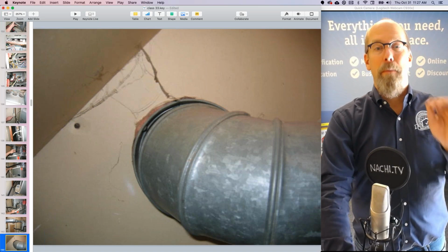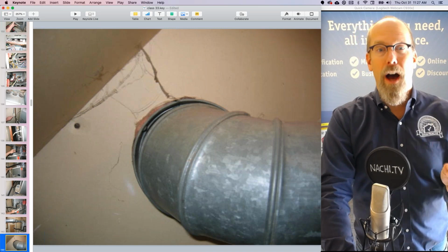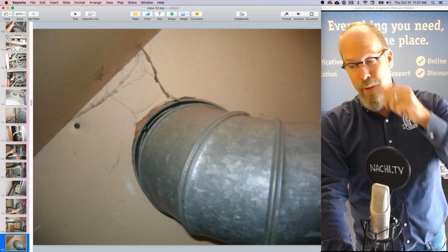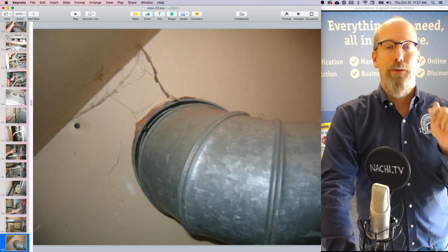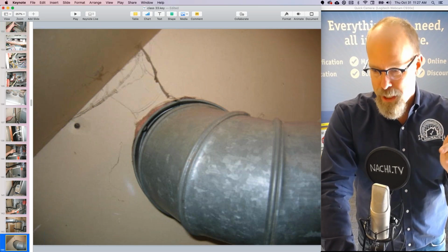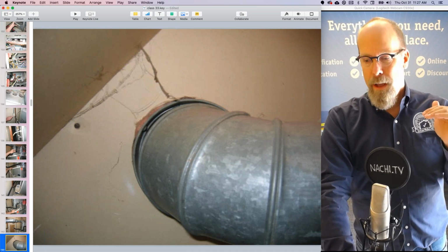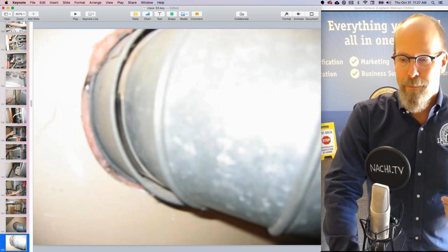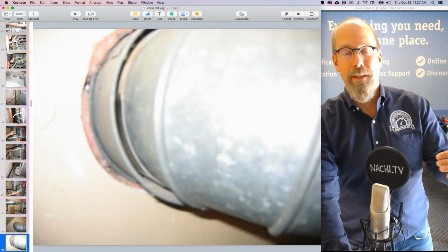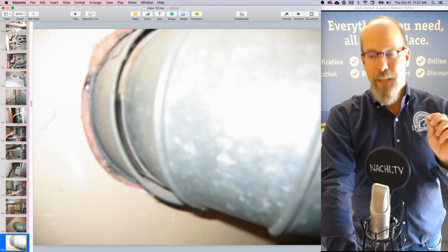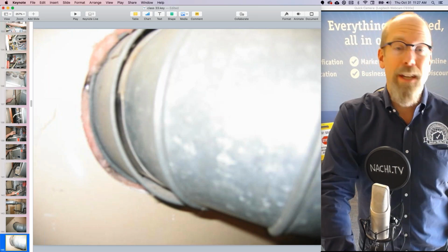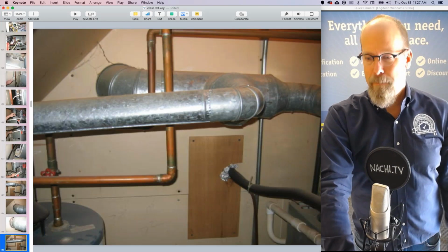I don't like combustible materials near a really hot furnace. And the exhaust pipe is in the hundreds of degrees. The exhaust gas is coming from a natural draft furnace heat exchanger. That's hot, man. So I'm going to call this out. And if the HVAC guy comes and says there's nothing wrong, great. Let that technician say everything's fine. There is no fire hazard. That's fine, I can do that.